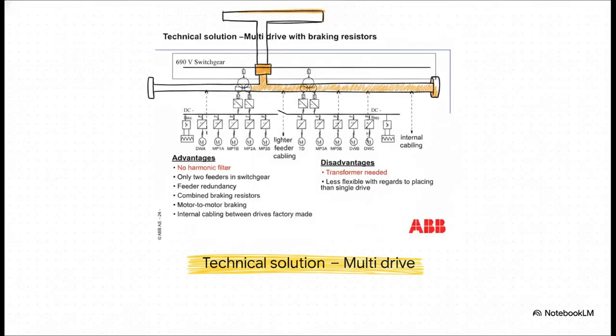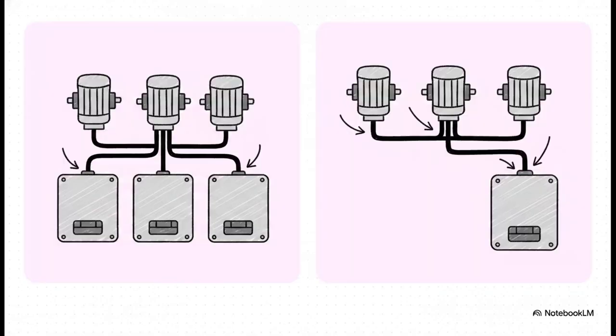Now contrast that directly with a multi-drive setup. The difference right at the supply level is night and day. It only needs one main supply breaker and a common rectifier sized for the entire group of motors. Power flows right into that shared DC bus, and from there, it's just lighter feeder connections branching off to each inverter. The absolutely crucial point here is the multiplier effect. Single drive literally multiplies your switchgear, your cabling, and your floor space by the exact number of drives you're running. Multi-drive, though, consolidates all that power supply into just one main breaker for the whole group.